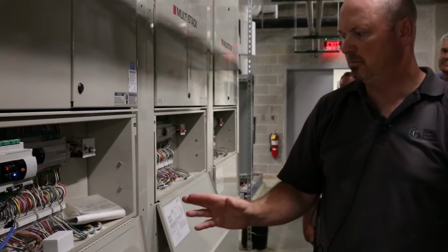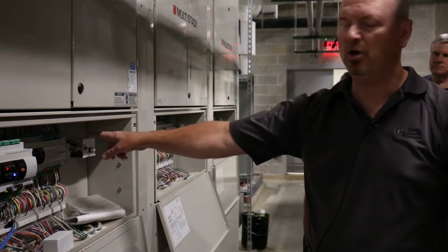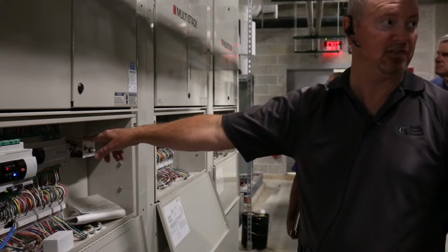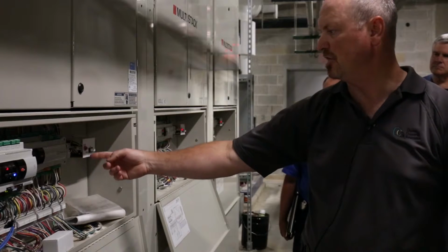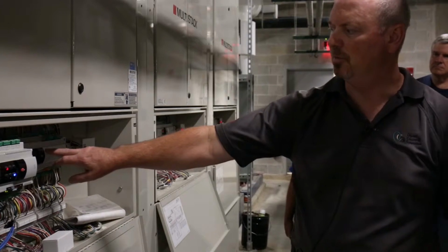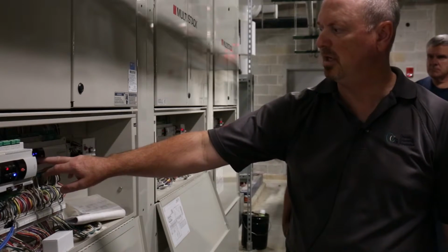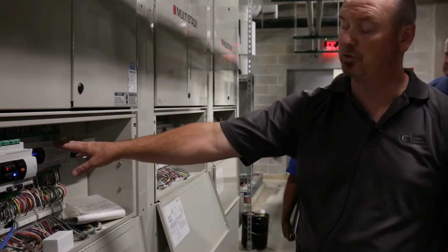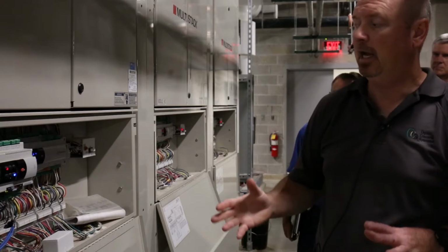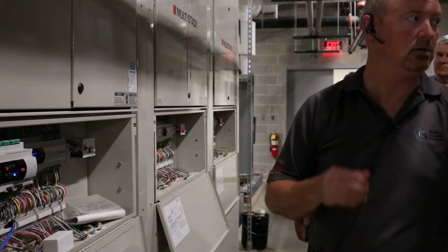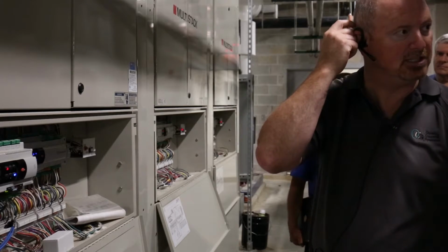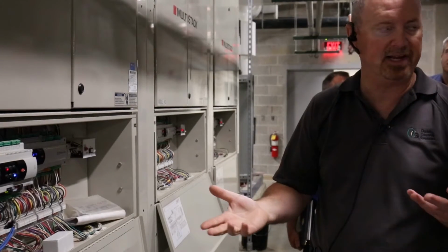The chiller can run in manual mode should the controls fail. You just switch this over to manual, go into a manual setup in your chiller controller, and set the set points you want. It could be different than what you're actually running the building at.